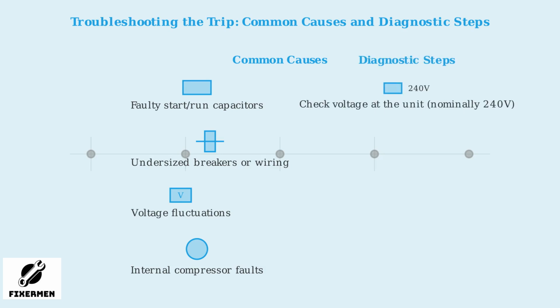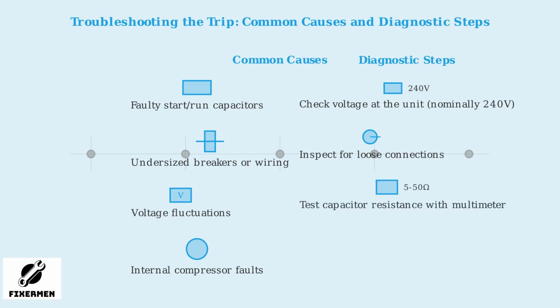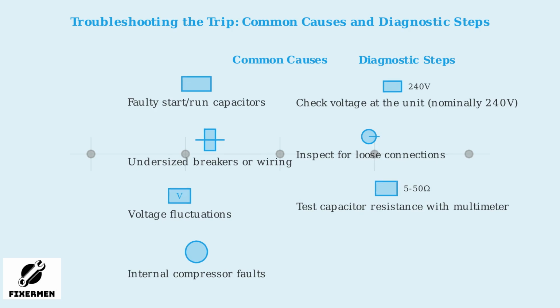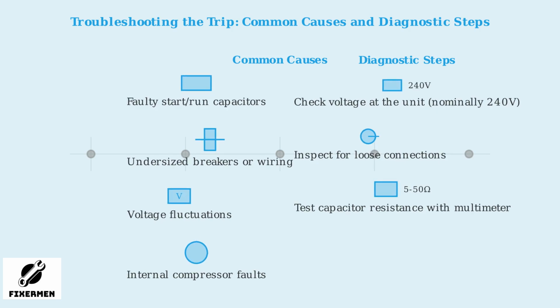To troubleshoot, first check the voltage at the unit, which should be nominally 240 volts for most Lennox systems. Inspect for loose connections that could interrupt the electrical flow. Use a multimeter to test capacitor resistance, which should ideally be between 5 and 50 ohms. These diagnostic steps can help narrow down the specific cause of the breaker tripping issue.